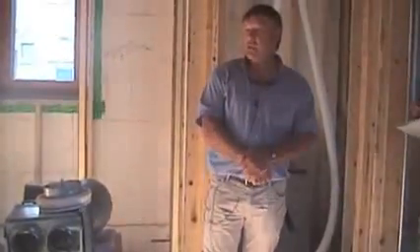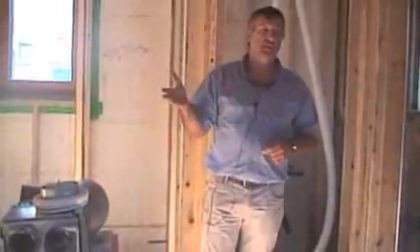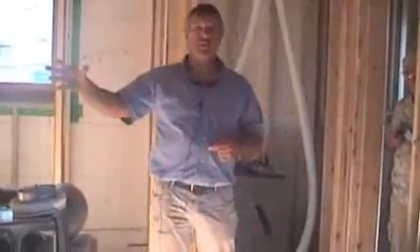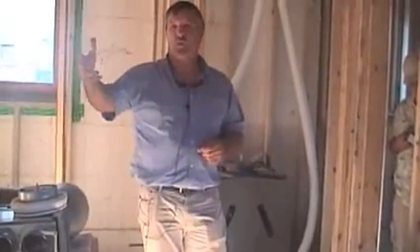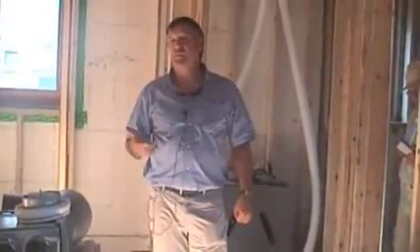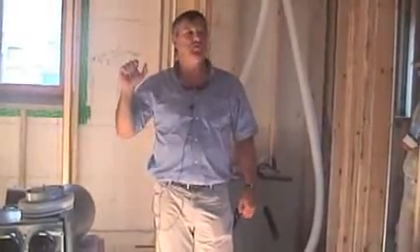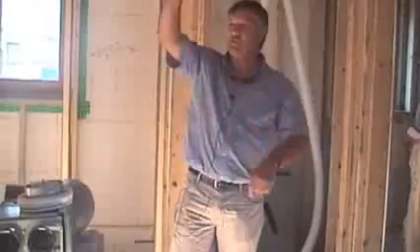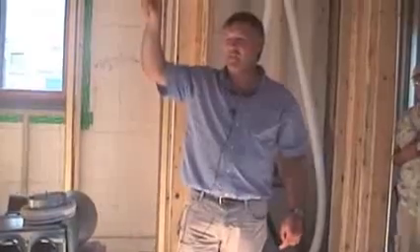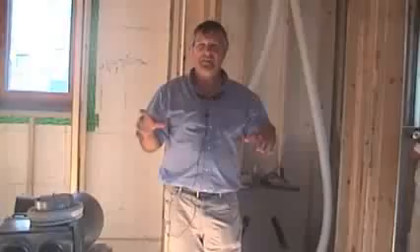One thing that we've had a big issue with in the market is tying ventilation into an air handler. Some people do. They put the supply air into an air handler, a return plenum of a furnace, for example, and use the air handler to distribute the air. And the problem with that, that's where we're getting some of this data. Every time the air handler changes speed or turns on and off, it changes the static pressure dramatically, and our unit goes, we've got data going from 60% to 90% recovery efficiency every time that air handler changes speed. So that's why we keep it separate.